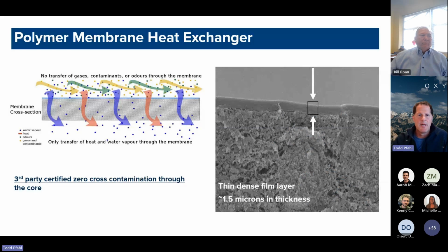And this polymer membrane is a pretty unique material. It's kind of like a thick plastic or a thick saran wrap that has a substrate applied to one side of it. That substrate is specifically formulated to only pass through a water vapor molecule. So it won't pass through any VOCs, any PM 2.5s, any odors, any viruses. So it makes for a nice material that has zero cross-contamination. We have total separation of your exhaust air and your outside air, which a lot of times is favorable, where we don't want any recirculation of the exhaust air that we're trying to get out of the building.